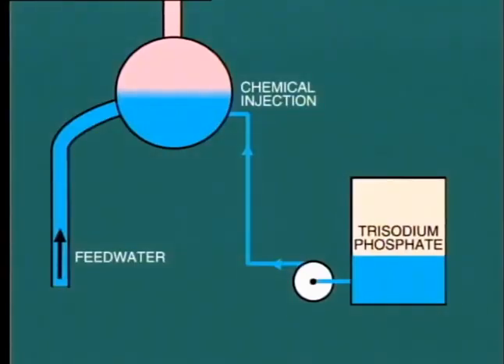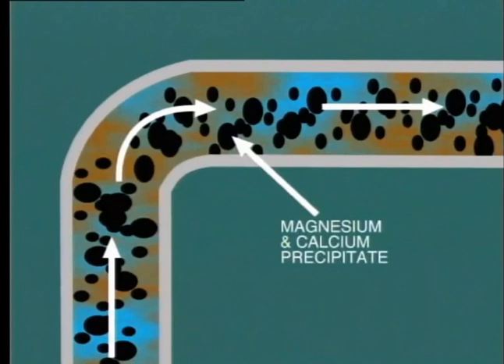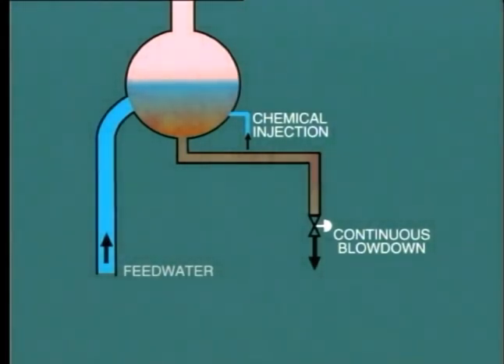We'll be talking more about corrosion later in this module. Even with all of these precautions and controls, there is still a tendency for the concentration of solids to build up in the boiler water. For this reason, an attempt is made to prevent scale formation by injecting a chemical dispersant such as phosphate into the boiler water. This is usually added at the boiler drum, so a high pressure pump is required. Phosphate has the effect of keeping the magnesium and calcium precipitate in suspension by dispersing the solid particles throughout the water, so that instead of forming a hard scale, the solids remain as a slurry to be discharged from the boiler through the continuous blowdown line.